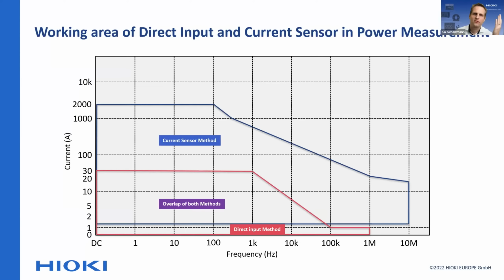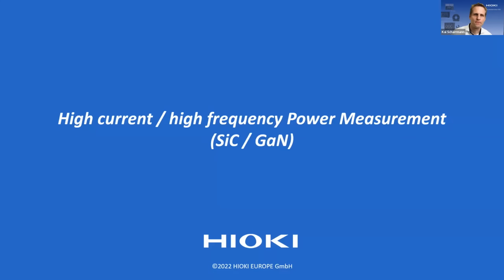On the other side, when it comes to high currents, we're not stopping at 30 amps or maybe 50 amps, but we're actually stopping at 2000 amps. That's the big advantage and disadvantage depending on the kind of power measurement you do: if you do high current power measurement, go for current sensors; if you do very low power measurement, shunts have an advantage.